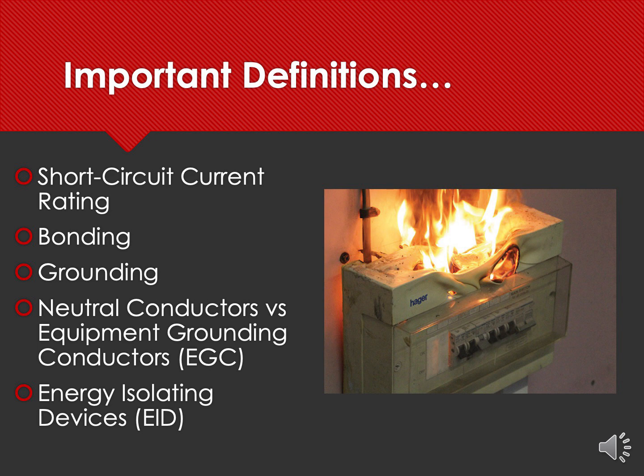If the bonding and grounding back at the panel itself, the source panel, is not properly connected, it's very important you understand that if the connections are not appropriate at the source, there could be a voltage between the neutral conductors and the equipment grounds on the same piece of equipment.